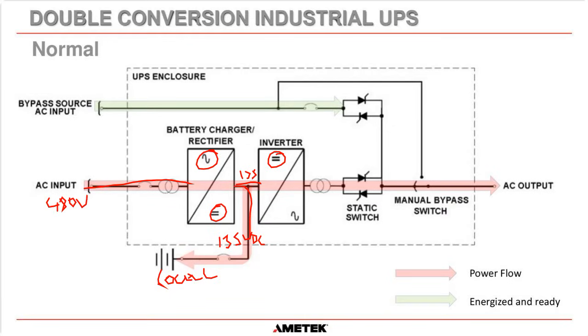And that DC gets changed back into AC. And that goes through a transformer, which makes sure that the output here is 120 volts. And then rather than go through a contactor, we go through a purpose-built static switch, which is rated for 200% of the load of the system. So it can quite safely handle all the power requirements for the load circuits. And then that goes out to our loads, sometimes through a manual bypass switch or sometimes through a remote manual bypass switch. And just like the commercial UPS, we do have our bypass available.